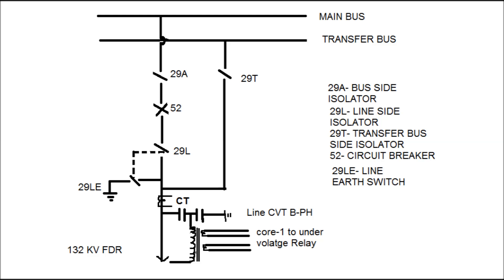The general arrangement for a transmission line feeder is shown in this figure. Here, 29A is the main bus side isolator, 29T is the transfer bus side isolator, 29L is the line side isolator, and 52 is the circuit breaker. 29LE is the line earth switch, and the CVT has been shown in the B phase.